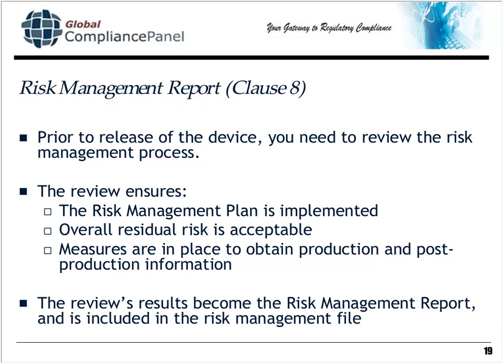and I'm going to document the review in the risk management report. So prior to releasing the device, I'm going to ask, did I implement everything in the risk management plan? Is my overall residual risk acceptable? Are there measures in place to obtain production and post-production information and to act upon it? So I'm going to look explicitly for those three things, and I'm going to document them in the report. So this is the review that I'm going to conduct. The results go into the risk management report, which is then put into the risk management file.